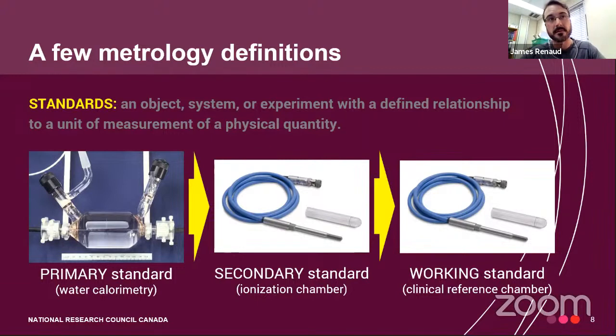Water calorimetry determines dose based not on first principles, well, just above first principles. Its calibration isn't dependent on the radiation quality. At the second layer, you have what is known as a secondary standard. These are generally more plentiful and less costly, but still serve as an approximation to the primary standard. An ionization chamber is a common secondary standard when it comes to absorbed dose. These are calibrated directly against water calorimeters. The other important aspect of the secondary standard is stability and precision.